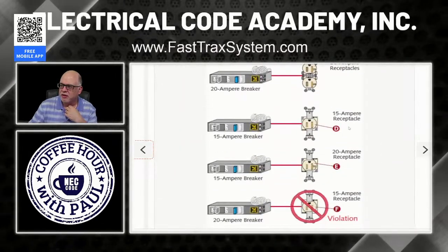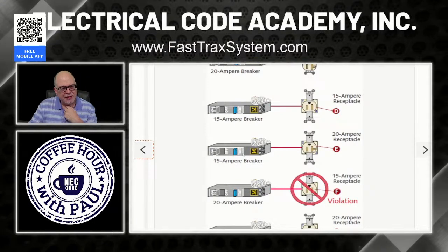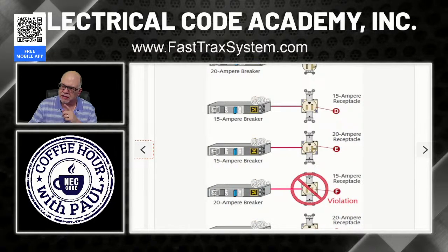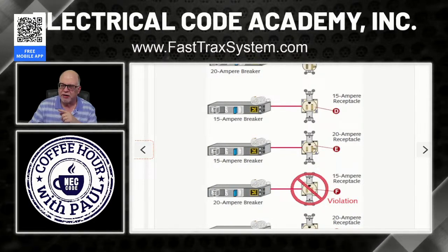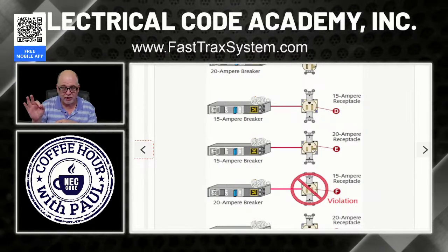So that was D. So remember what I just said? What about this 20? Can I put a 20 on a 15? Absolutely. Because as long as the rating of the receptacle is equal to or greater than that of the overcurrent device, when it comes to these simplexes here, absolutely, I can put a 20 amp single on a 15 amp, okay? Now, of course, I could put that single 20 on a 20. That should be a no-brainer.